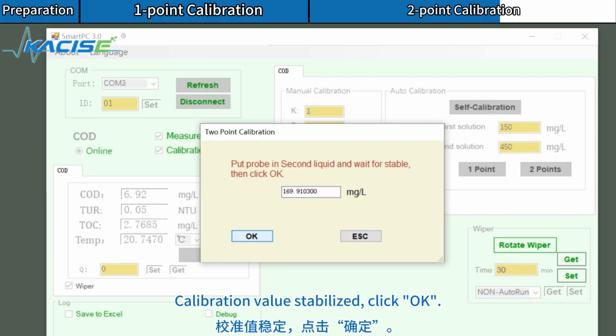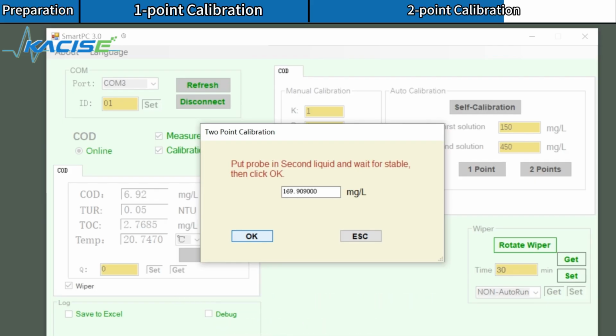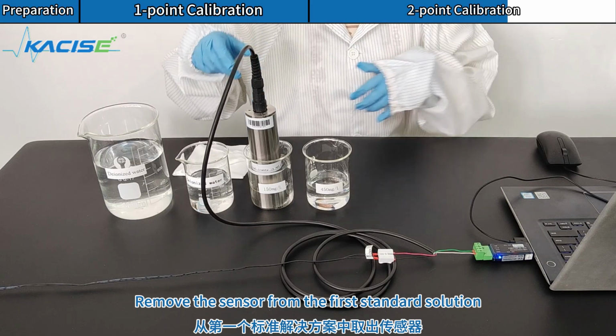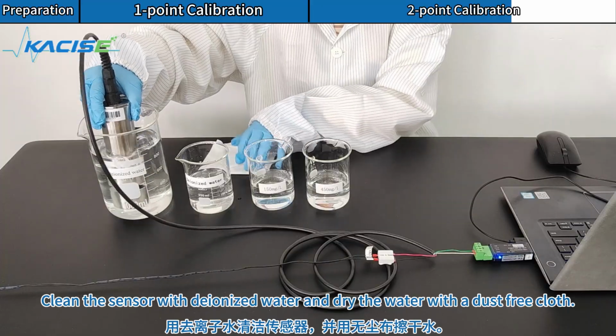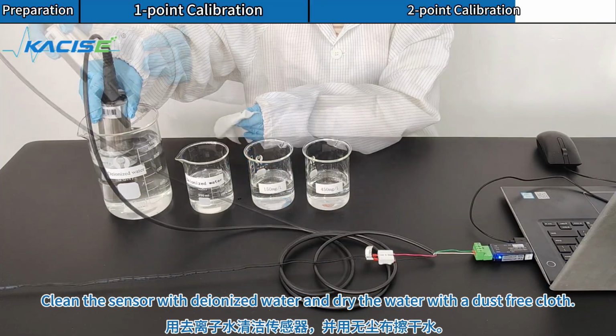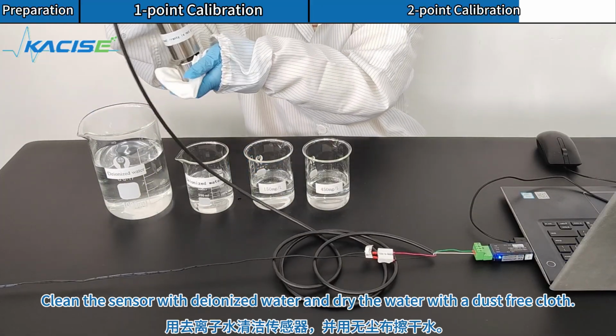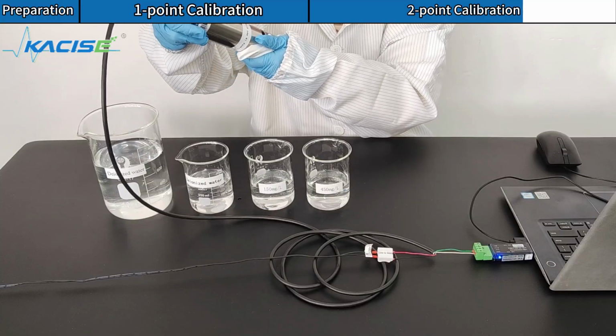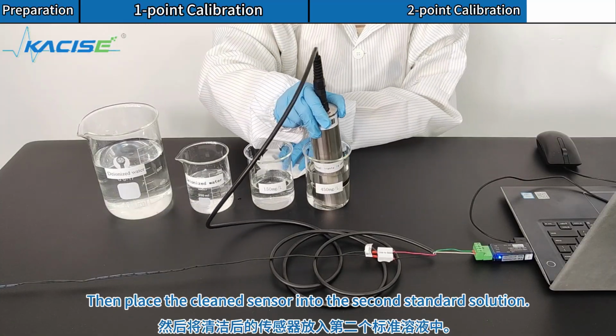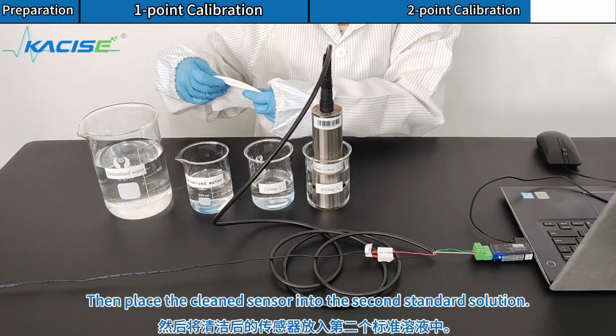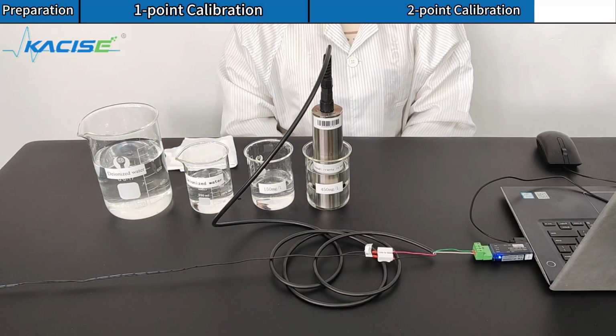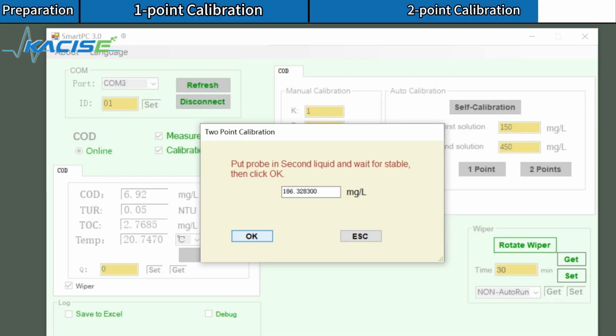Calibration value stabilized. Click OK. Remove the sensor from the first standard solution. Clean the sensor with deionized water and dry the water with a dust-free cloth. Then place the cleaned sensor into the second standard solution.